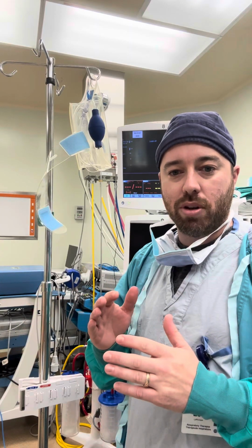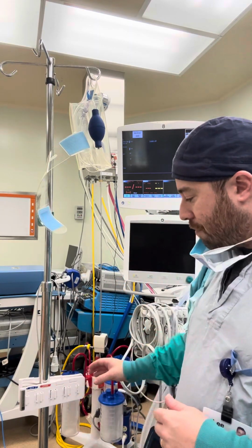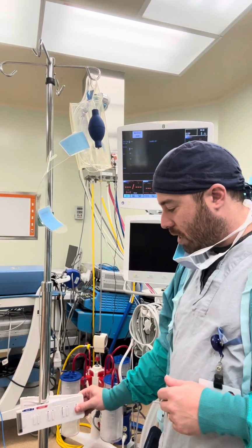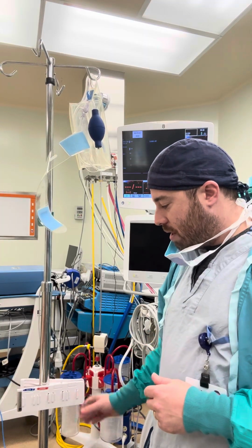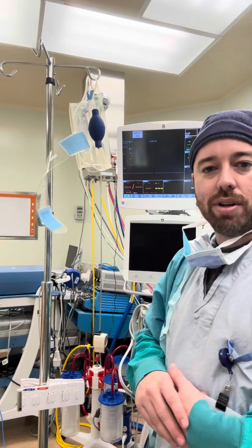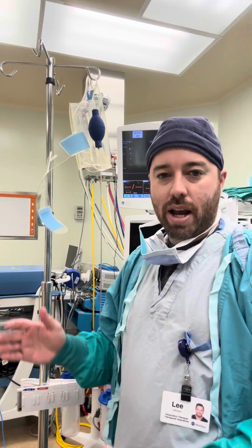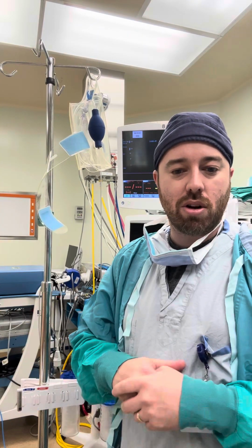This pressure system not only allows that, but also has the ability to be zeroed, so that we can zero it for where the patient currently is sitting on the level, and that allows that level to be moved up and down according to the bed height, or where the patient's at, or the size of the patient, or any number of things.